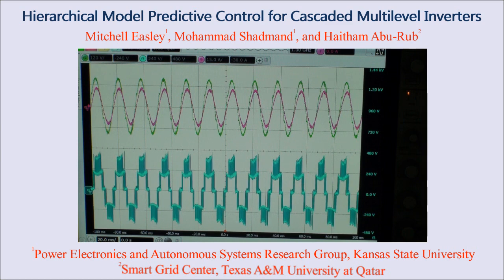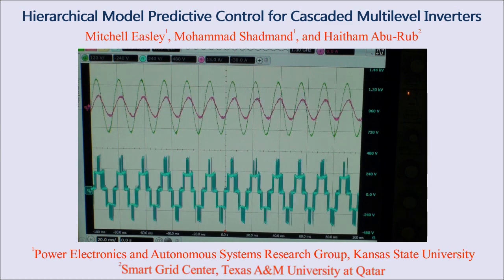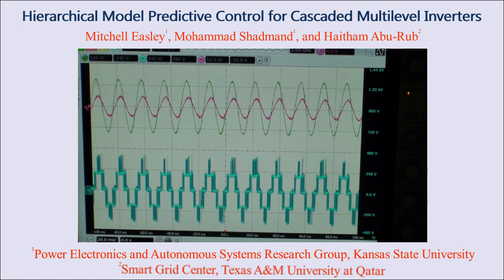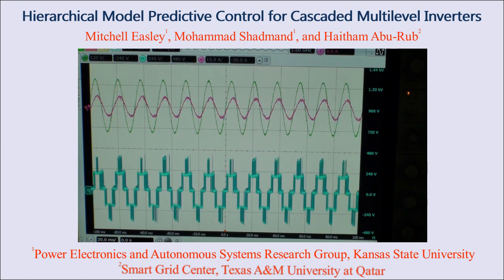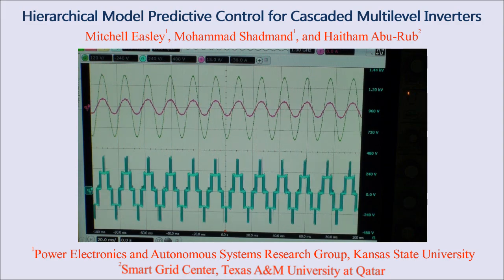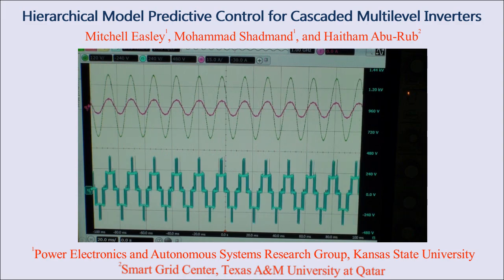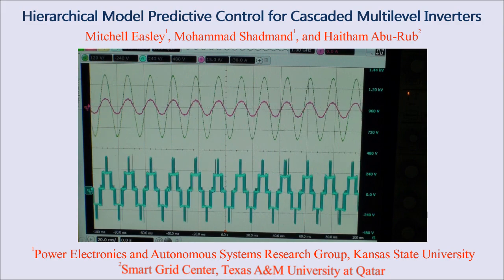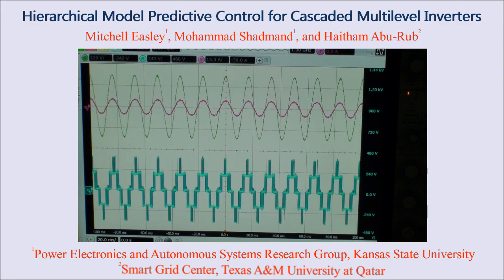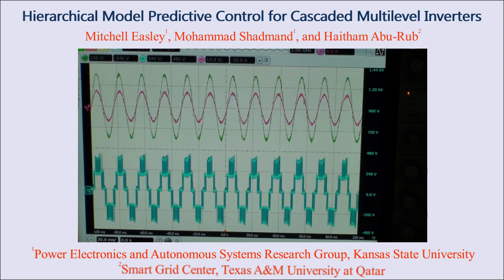The reactive power injection is easier to see when I reduce the power reference back down to 500 watts. The controller stops injecting reactive power once the grid returns to normal condition. Finally, the power reference returns to 1 kilowatt.